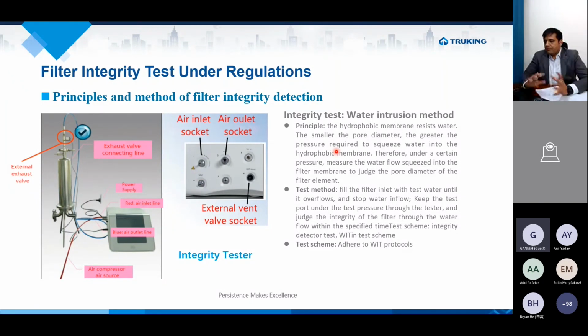So what is the principle? The membrane of the filter being used is hydrophobic in nature, so it resists water. The smaller the pore diameter, the greater the pressure required to squeeze the water into the hydrophobic membrane. So it's very obvious. Therefore, under a certain pressure, we measure the water flow squeezed into the filter membrane to judge the pore diameter of the filter element. So that is basically how the principle of water intrusion works.